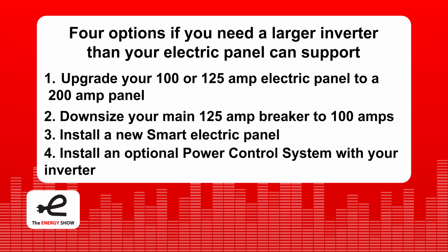Now there are 2 new options based on smart electric panel technologies and smart inverters. One option is to install a new smart electrical panel that senses when you get to these limits—you may have 100 to 125 amps—and it prevents you from going over, which prevents that breaker from tripping. It does this by automatically shedding load.